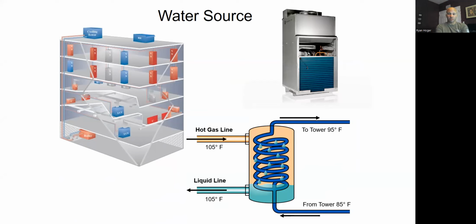You could connect them to the domestic water. A lot of times that's called a pump and dump system. You run the domestic water from the city water through there, run it through the heat pump, add heat to it or take heat out of it, and then dump the water down the drain. There are buildings that do that. There's nothing that does that that's been built in the past like 30 plus years. That's no longer allowed by any codes, but there are still buildings that have it because that's what they had from day one. And it's some big giant building, and there's not really any good way to add a cooling tower and a boiler to it. So you're just basically dumping water down the drain. It's super wasteful for water, but that does exist.